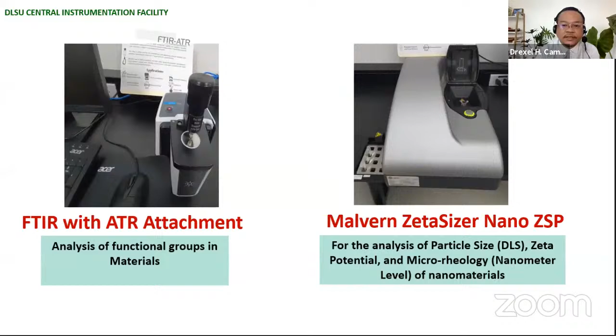And we do have a UV-vis spectrometer, but this is not the usual UV-vis you're familiar with, where we put our sample in a cuvette in solution and place this inside the spectrometer. Our equipment is equipped with a specular reflectance attachment, so that we can analyze large samples as well as solid samples and films and glasses. And if you have some coatings on your glasses, we can analyze the amount of UV absorption in there.